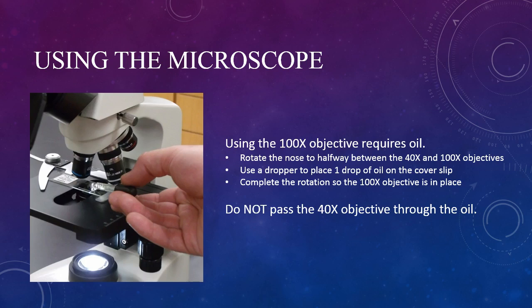It is important not to run the 40x objective through the oil. It can become contaminated by oil seeping into the objective lens and fouling the inside, in which case the objective must be taken apart and cleaned in order to be reused.